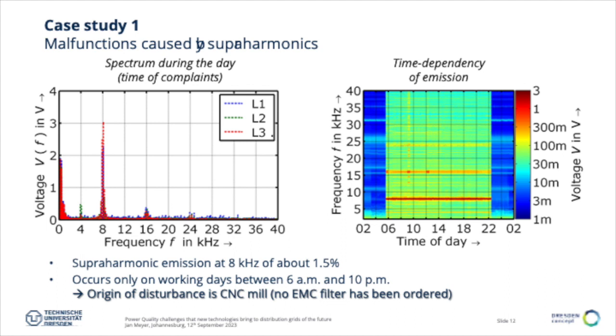And indeed, when we approached this little company having the CNC mill issue, they said, yeah, because of energy efficiency, we changed our variable speed drive from a classical one to one with active front end. And they only forgot to order the EMC filter. So this was easily sorted out by just buying the EMC filter. They first tried it with a cheap one, but this did not work as well. So they really had to buy the one from the manufacturer of the drive and converter as well. And then it has basically been solved, but there were quite a lot of rumors at the utility about this, because nobody really knew how to measure it at all, if we would not have been there.